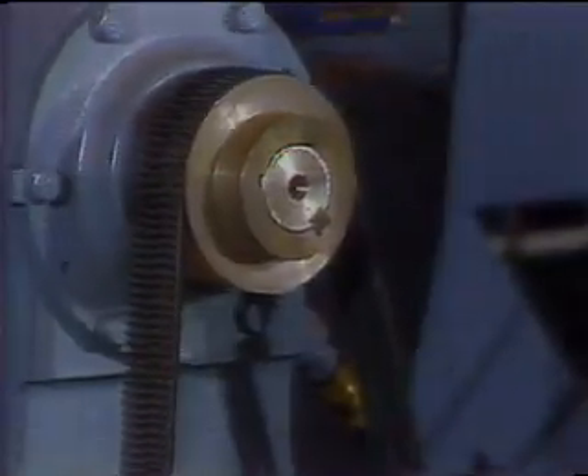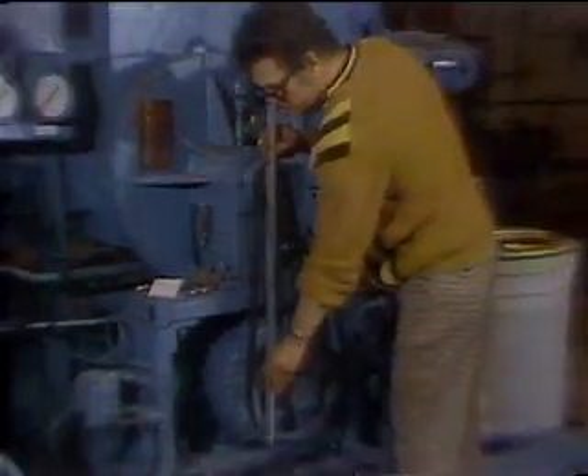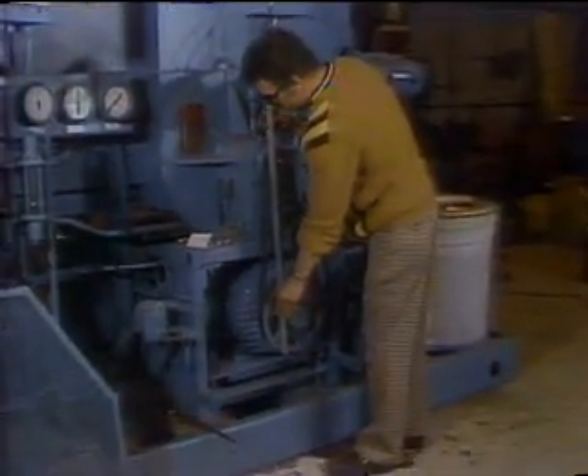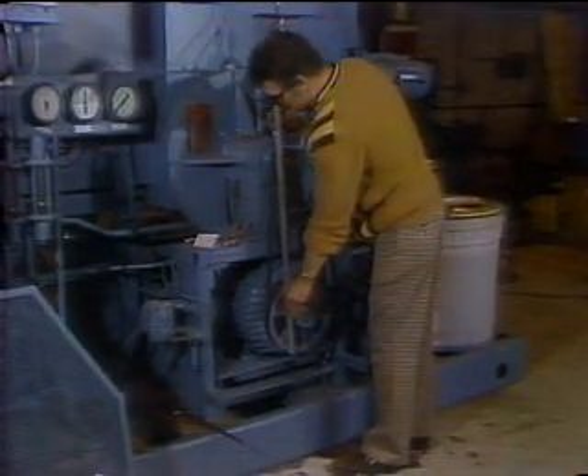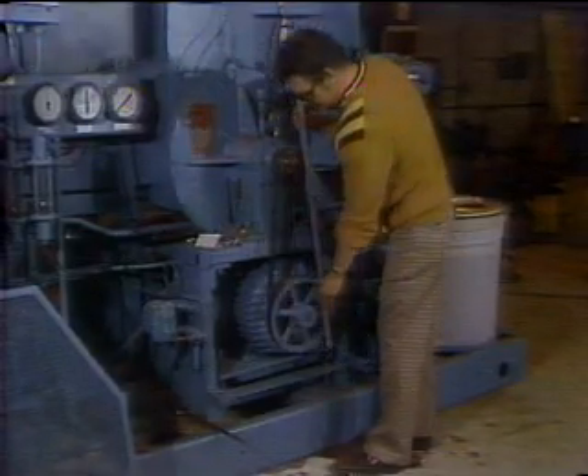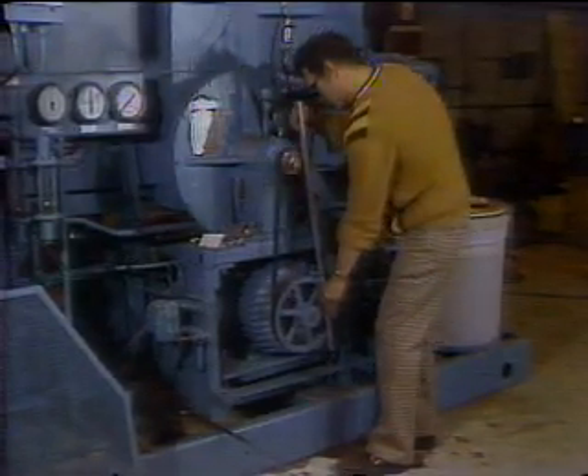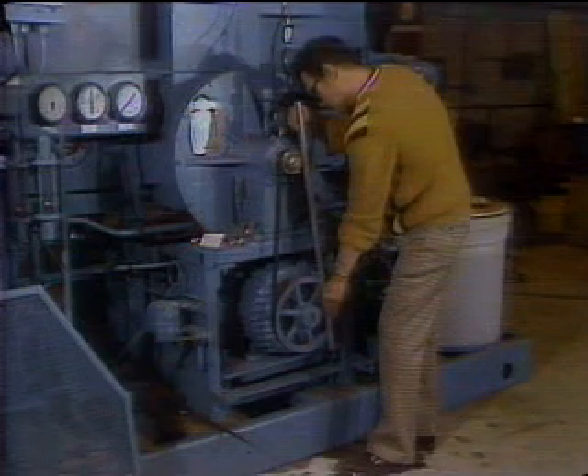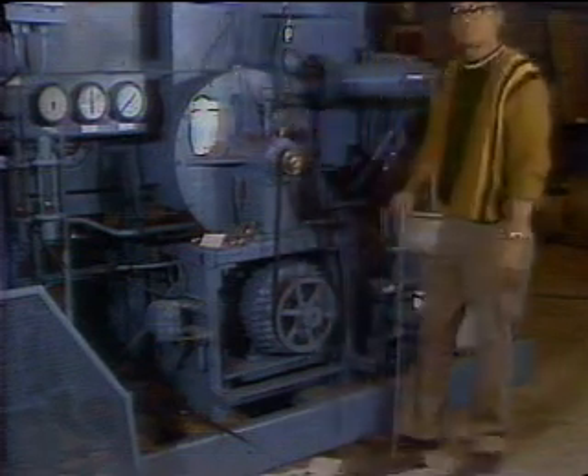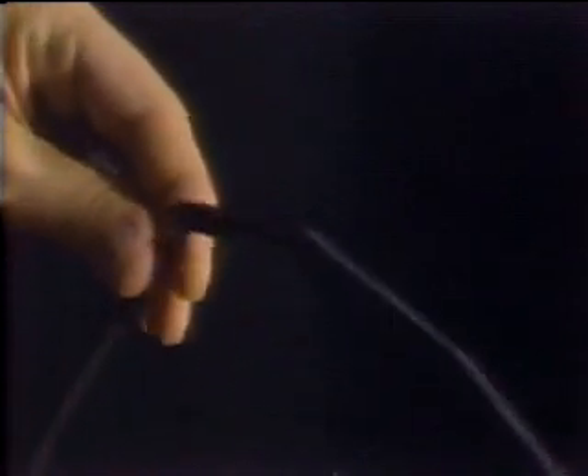Then a quick check of the centrifugal compressor. Use a straight edge to check alignment. Hold the edge flush with the motor sheave and move it into the compressor sheave. The straight edge should just touch the face of the compressor sheave. The other side should be the same. If it's not perfect, it'll ruin your belts real fast, so an adjustment will have to be made. If the sheave is aligned properly, but just forward or backward of where it should be, loosen the set screw on the motor sheave and tap it into perfect alignment.